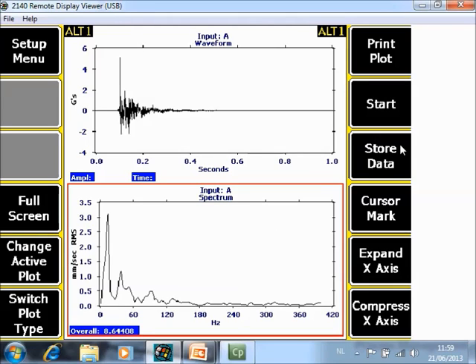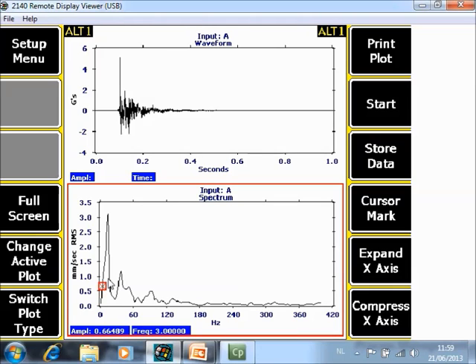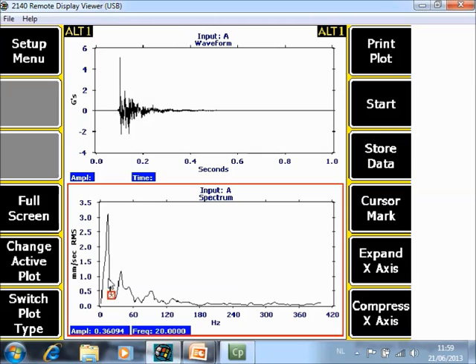If you want to know the natural frequencies of the system you can now install a cursor on it. You see that one natural frequency is 14 Hertz and another one is around 37 Hertz.